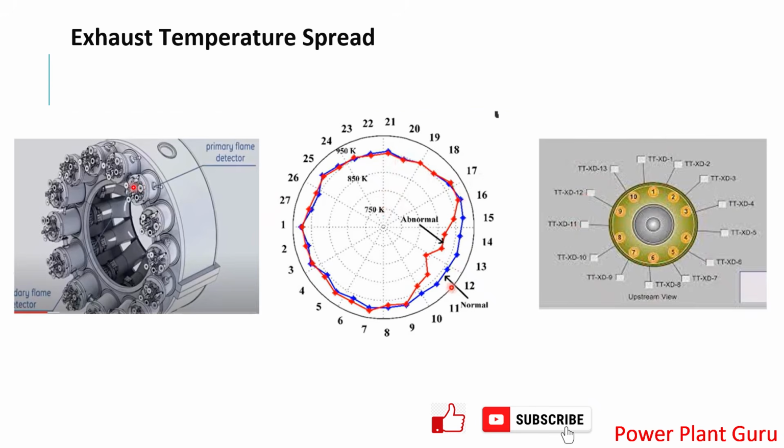Let's say, for example, this particular nozzle is fuel deprived or deficient. Then the air is the same, the fuel is less, so what will the temperature be here? The temperature would be somewhat reduced compared with the others. That's how it may also give you a shift in the exhaust temperature.